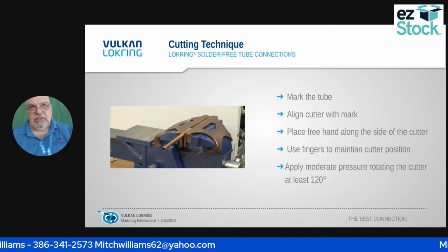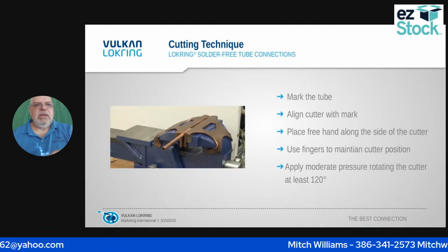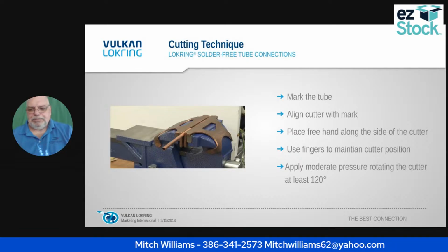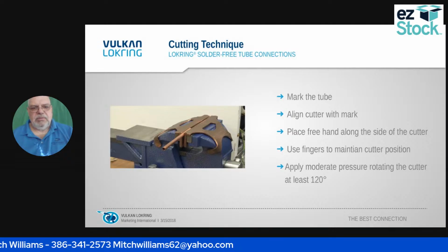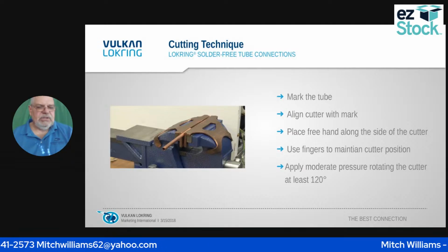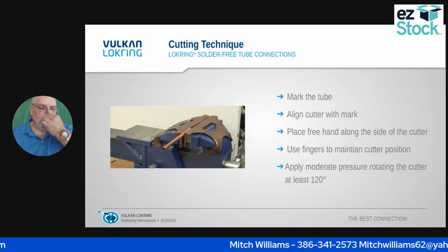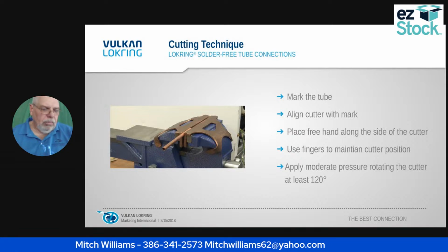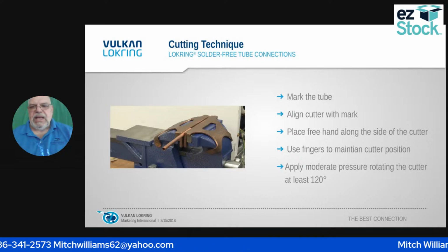One of the other things is if I try to use too much pressure, it not only chips the wheel, it can actually close that down. As small as the tubing is, it can close it and restrict the tubing size. If I use too little pressure, it will try to walk up the side of the unit.